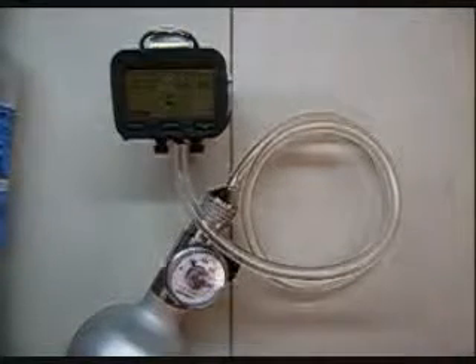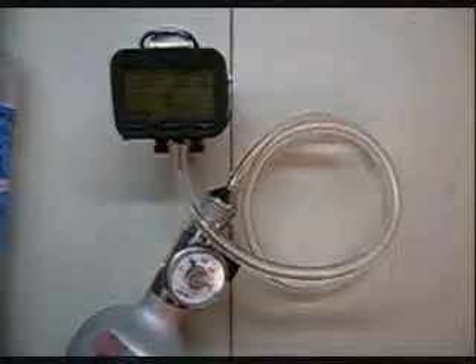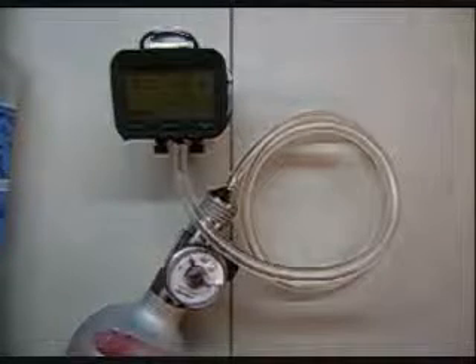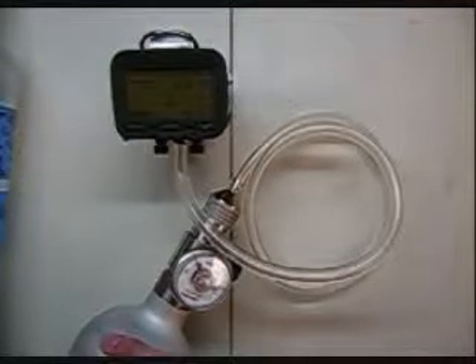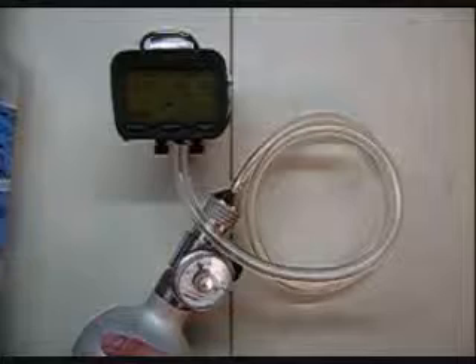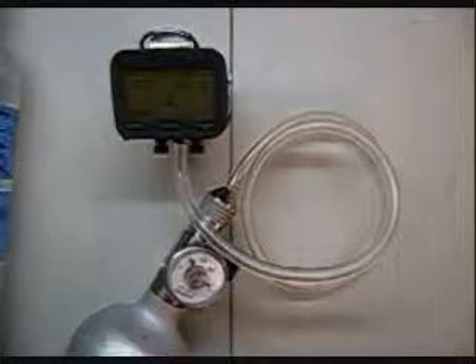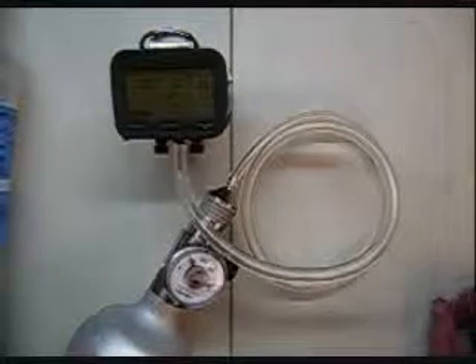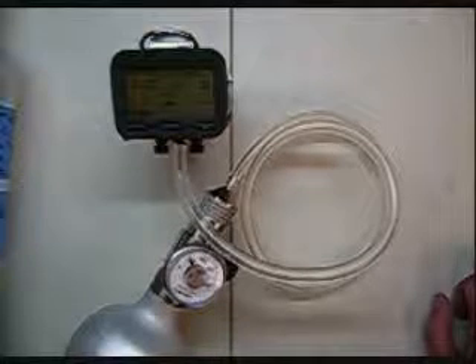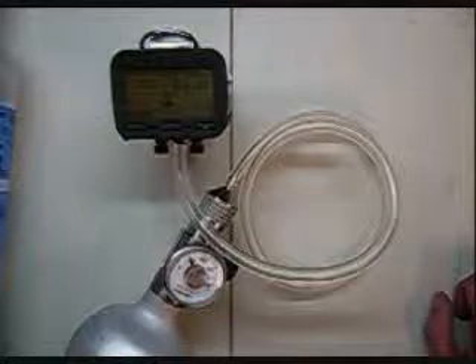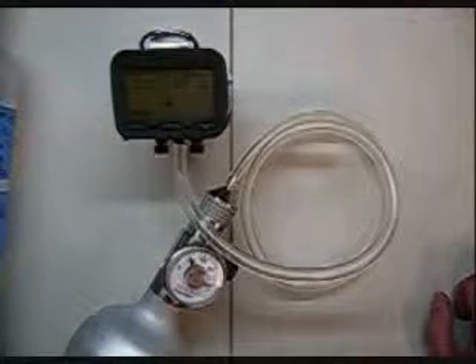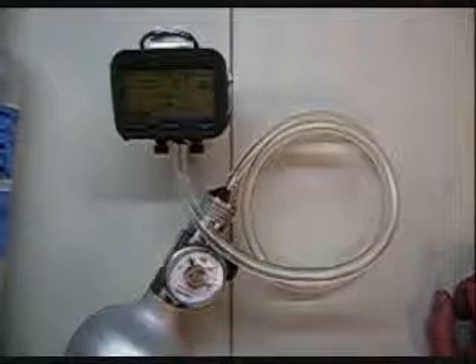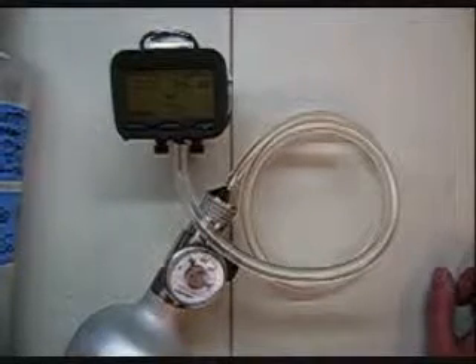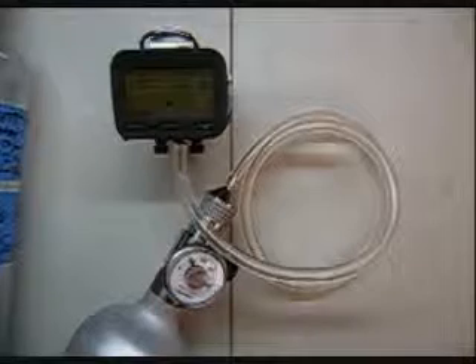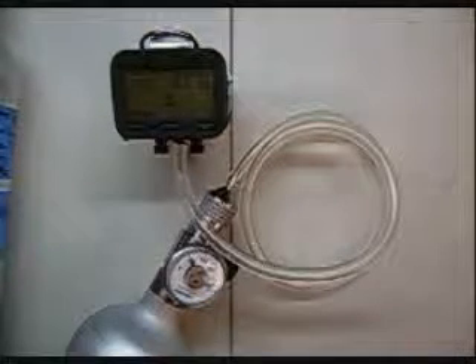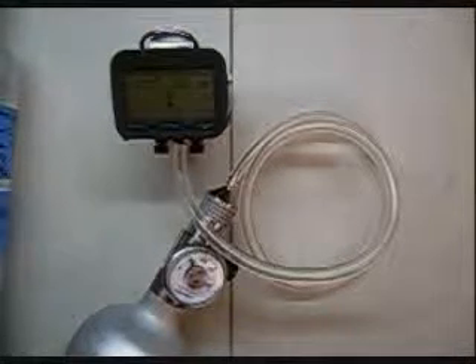The order that we're going to go in is to start with the methane and air. The next one is going to be the ammonia, and then afterwards we're going to go to the sulfur dioxide. The procedure for all these is exactly the same as what we're doing right here. The only difference is that, because of the reactivity of the gases involved, I would leave about 5 minutes or so while the gases empty out between calibrations. You won't need to re-zero, but just leave that time during calibration.